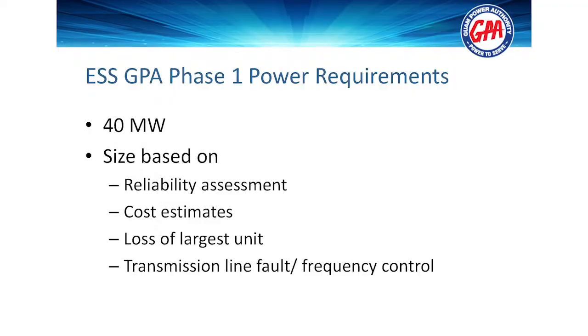So what do we do on GPA? Phase 1, 40 megawatts. They went through a lot of studies on this, a lot of determinations, loss of the largest unit. And the biggest issue, I'll stress again, is what's acceptable criteria for your reliability. When we actually set the criteria for if you don't want to have any load shedding for your loss of your largest unit, the BES went up to 65 megawatts. Pretty huge increase, 50% increase in load for just that one criteria.